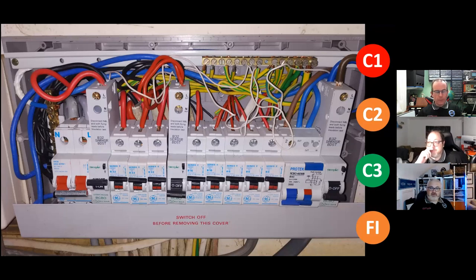And some positions of boards, you just cannot get the neutrals in properly. And confidently, they just put them way beyond reach. That's a perfect example of a board that just isn't a manufactured assembly. It's just not been considered as a holistic assembly at all. No. Too much copper showing on top of the terminals.